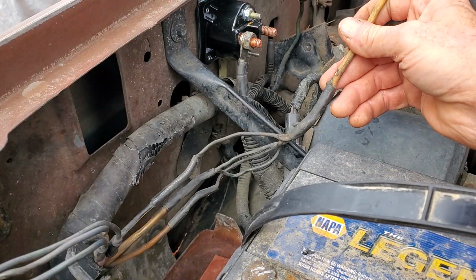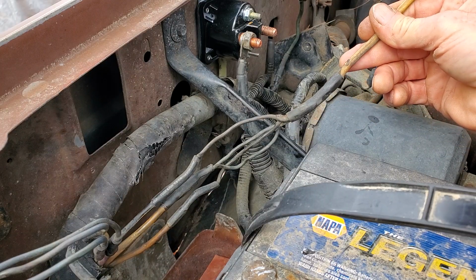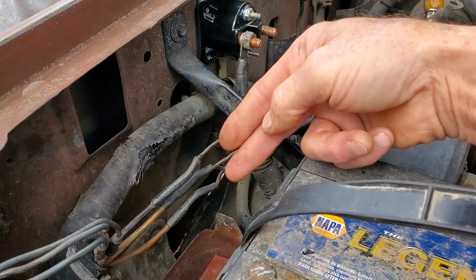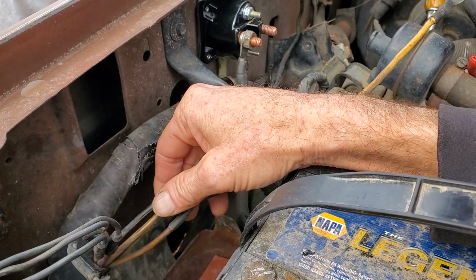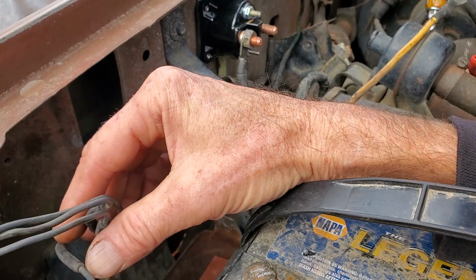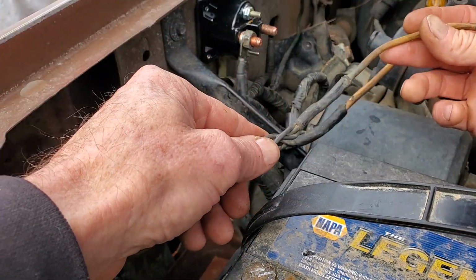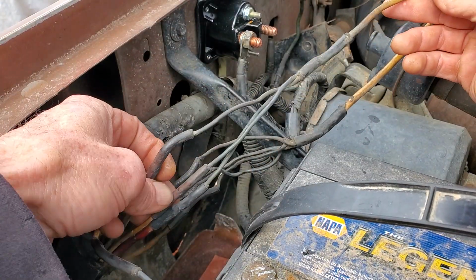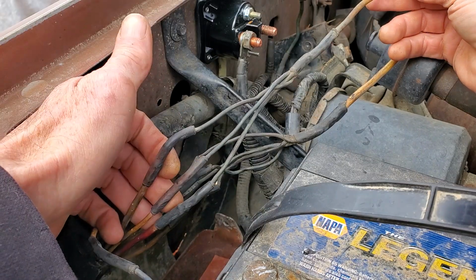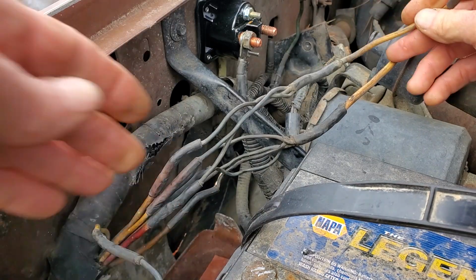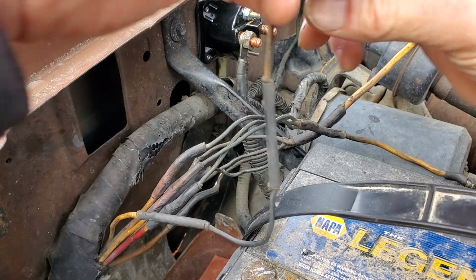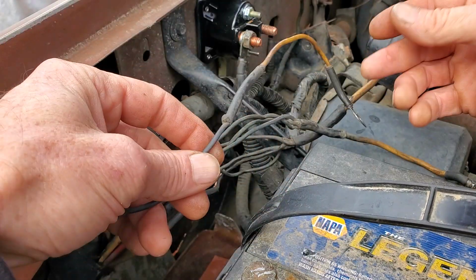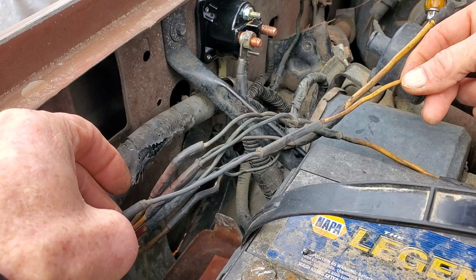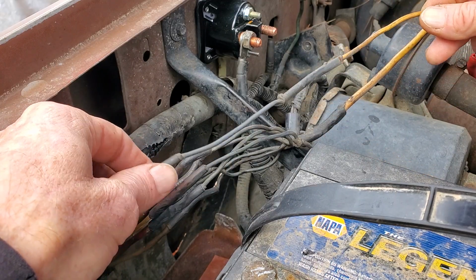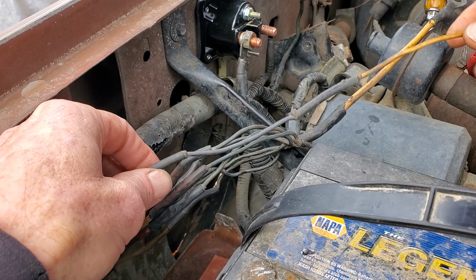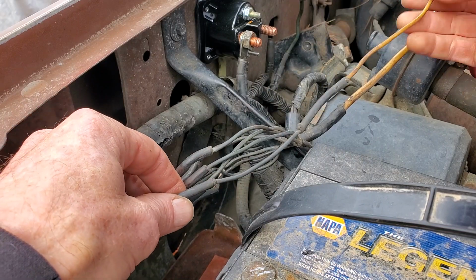So here we got a fuse link, a big yellow, that's broken up into 4 branches, feeding 4 individual circuits, and we saw that on the schematic. Here's another yellow fuse link that's branching out into 3 different circuits. And here's another fuse link, yellow, that's going out to 1 circuit, which if you follow the schematic, you'll probably see that it does another branch downstream.